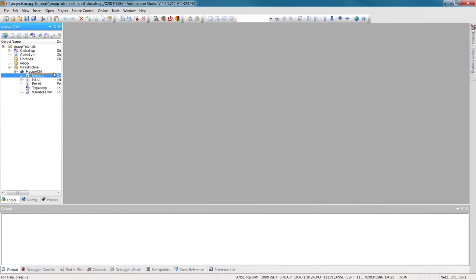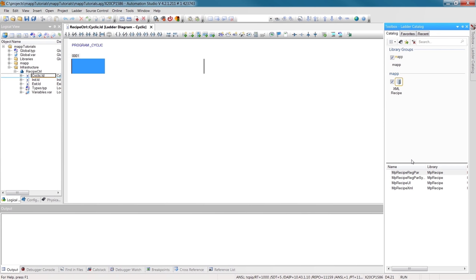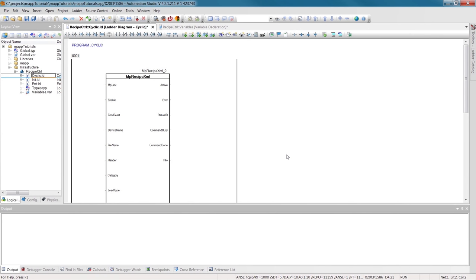To allow the user to load and save recipes, we'll add the MAP component MPRecipeXML. Using the MpLink input, we establish the connection to the configuration object that we created before, named GLINKRecipe. We'll enable the component by setting the enable input.